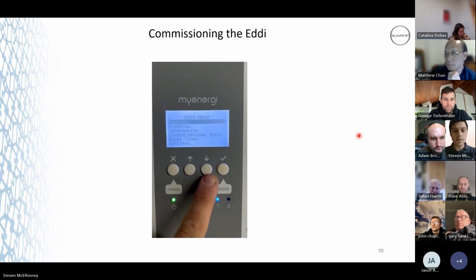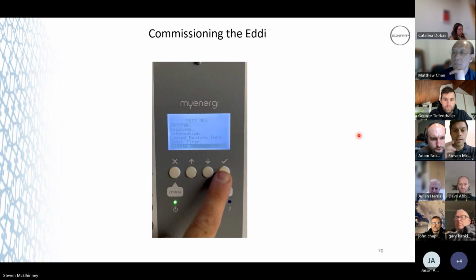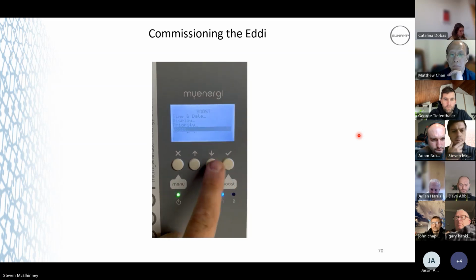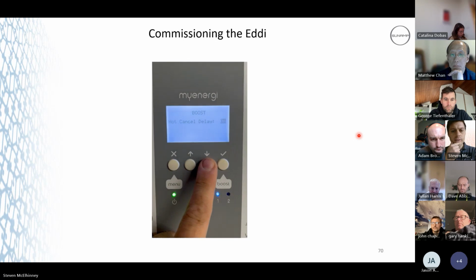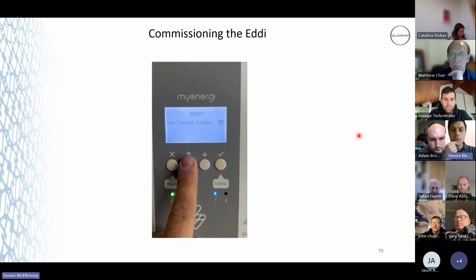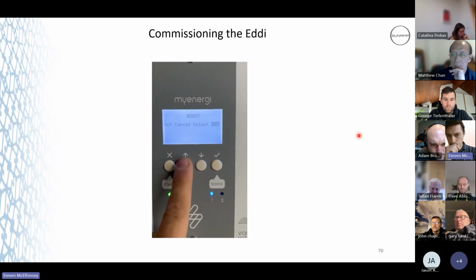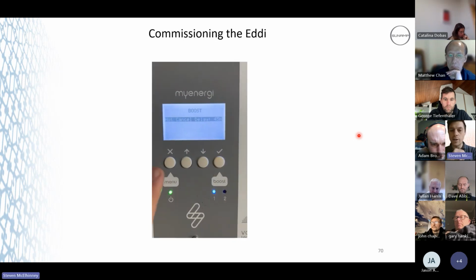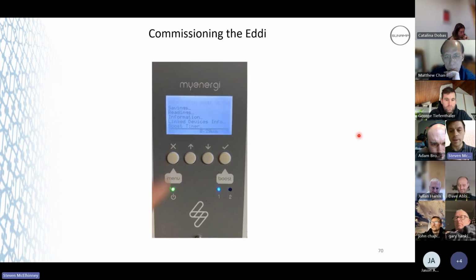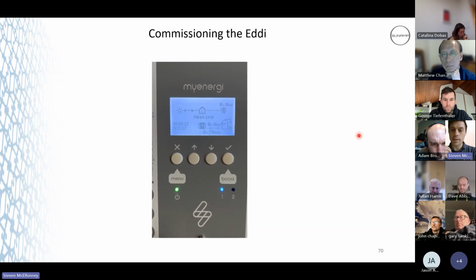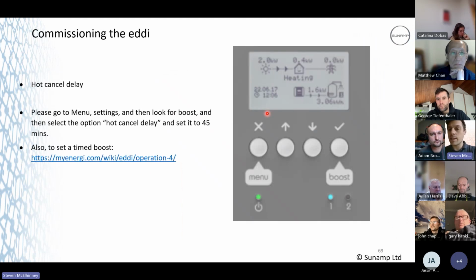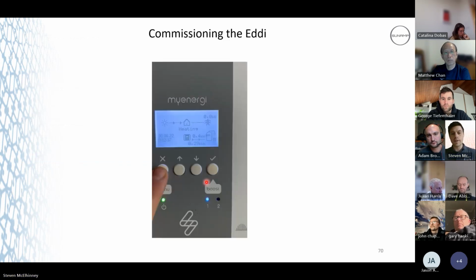So, quick video here. I think this is the old firmware. What we say in our manual is set it to 45, but what I would say for the 210 and the 300 is set that to 60, just to give it that little bit extra. Because it's bigger, it'll take a little bit longer for that heat to start flowing and circulating through the battery. That's important. And then you've got the other things as well, like set your time and date, initially set your time boosts if the customer wants one set, and that should be you for any off-peak tariffs.